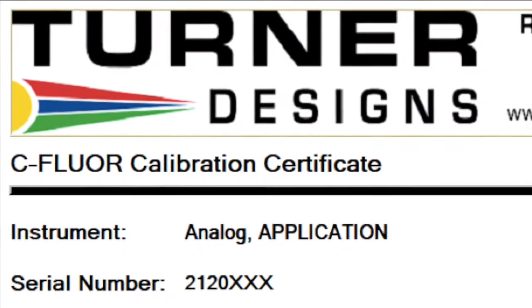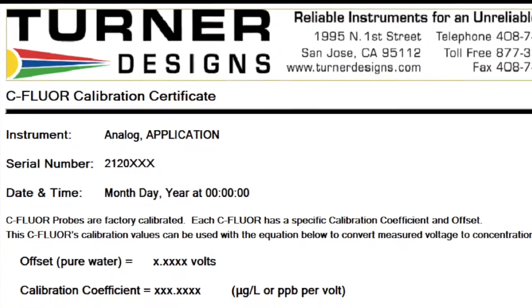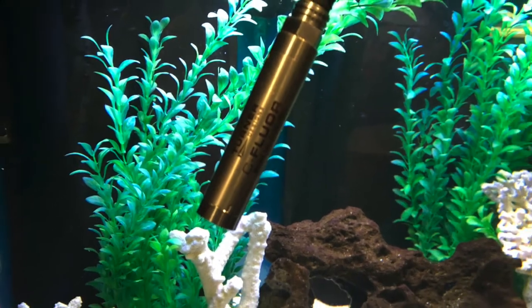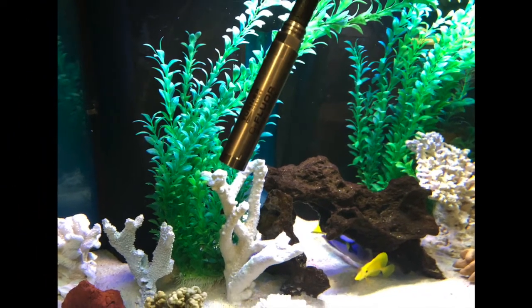Factory-calibrated, each C-FLUOR probe ships with a calibration certificate used to convert the analog output signal to a specific concentration estimate. The titanium construction allows a depth rating of 2,000 meters as well as superior resistance to corrosion, an important factor with their capability for extended deployments.